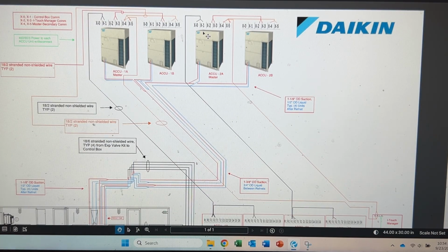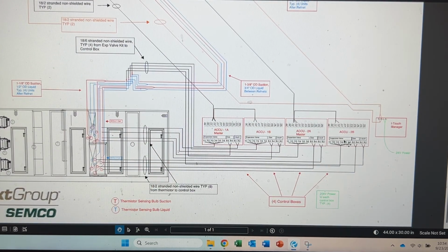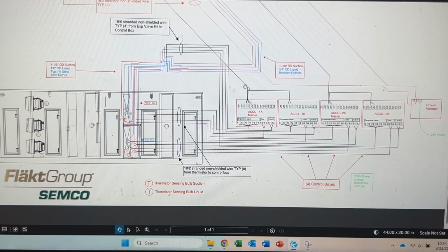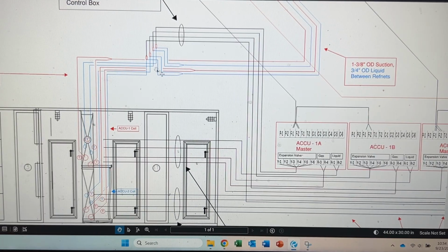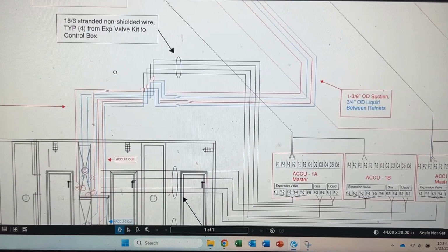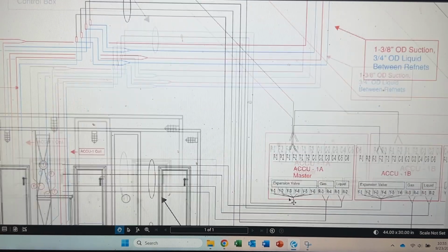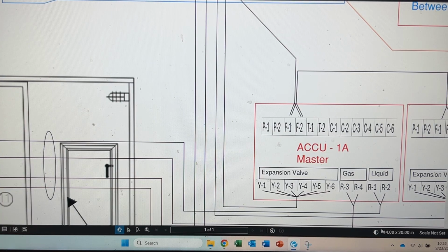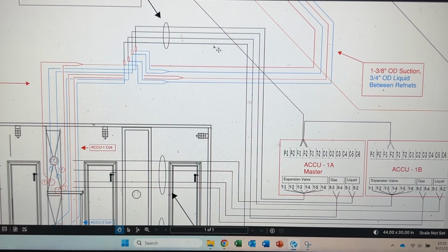I have all the terminals here and how they connect to each other, then how they get back to these control boxes indoors. So now, our expansion valve kits were piped in line downstream from the ref net fitting, and we did run 18/6 stranded, but there were only 4 wire terminals on this particular expansion valve kit. So we did not utilize, I believe it was Y5, for whatever reason. But anyways, basically there was a wiring harness at the expansion valve with like a 3-foot whip on it. And we ended up just removing that whip and connecting to the harness right at the expansion valve.